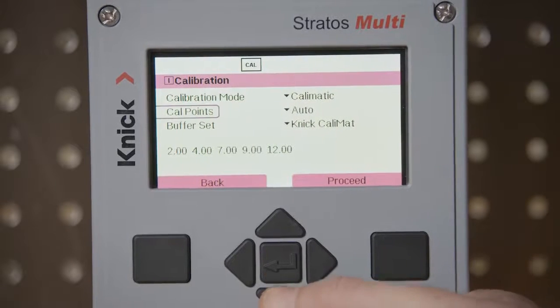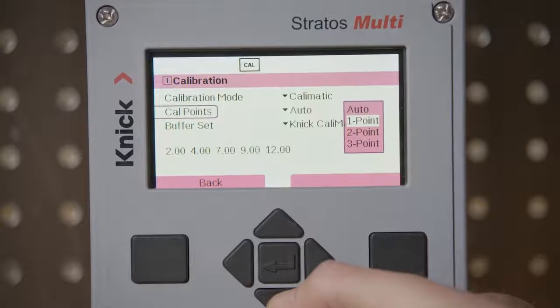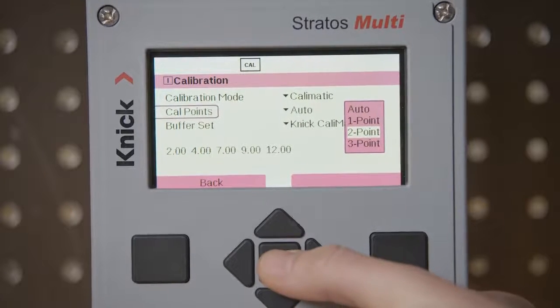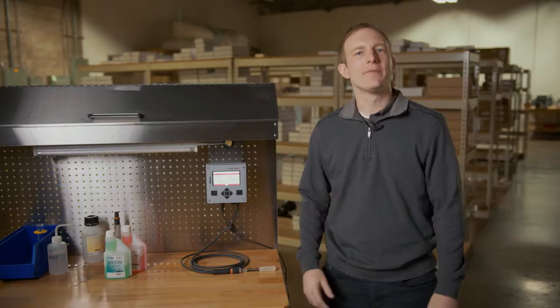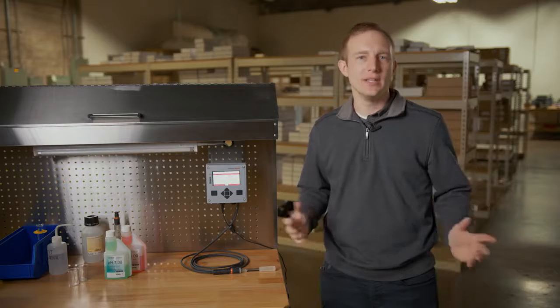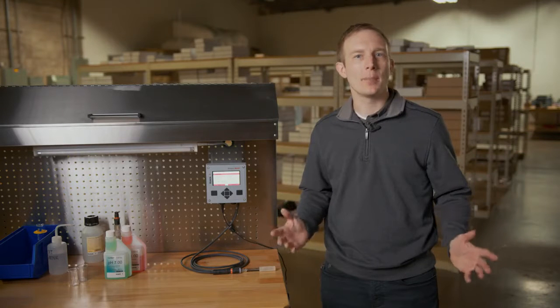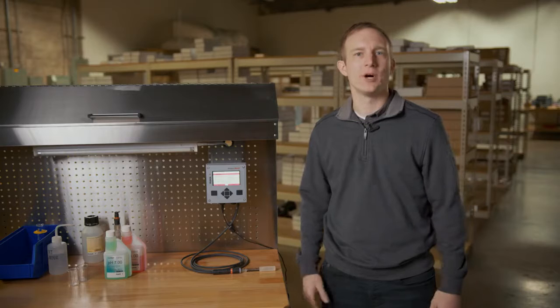Under the number of calibration points, we will select 2 point and then move on to the selection of our buffer set. As we are performing an automatic calibration, it is very important that we have the proper buffer set selected in our Stratos multi-transmitter. This ensures automatic recognition of the buffer values as well as automatic temperature compensation during the calibration process.